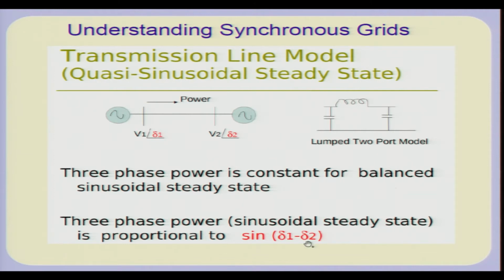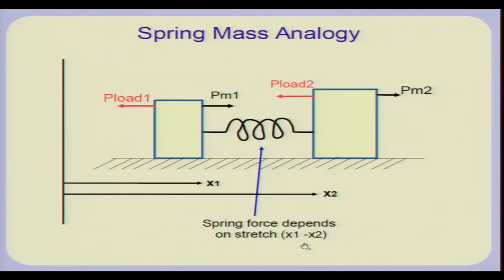So the important thing to remember is that this stretch of the spring provides a restorative torque only if your stretch is not too much. If, because of some disturbance, the spring stretches too much, the restorative torque, which is proportional to sine delta 1 minus delta 2, can become negative or reduce, and in such a situation the generators may not stay together.